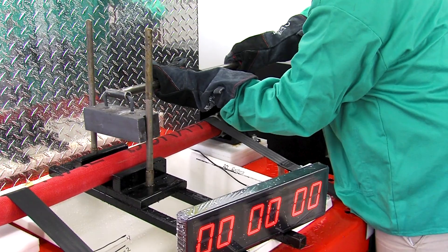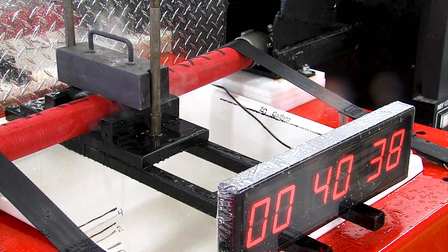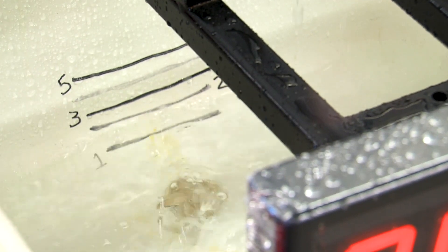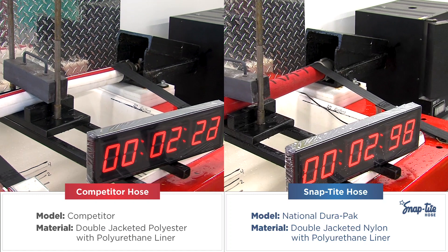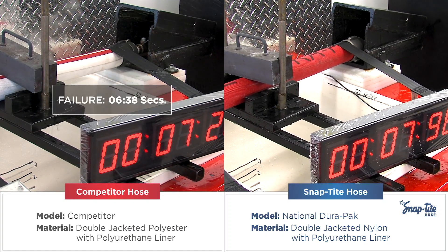The hot block is placed directly on its surface. The time to 20 psi pressure drop is recorded. 150 psi dynamic pressure is then applied and leakage rate measured in gallons of water per minute. The same tests run on competitive products reveal significant differences.